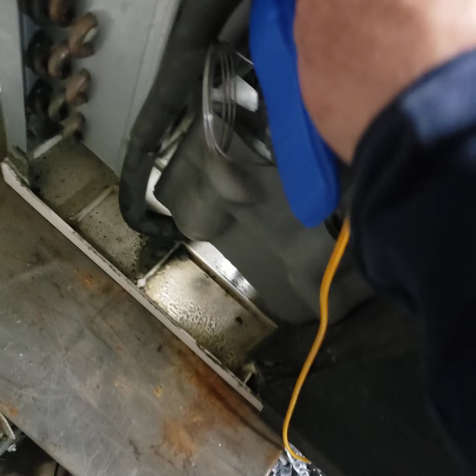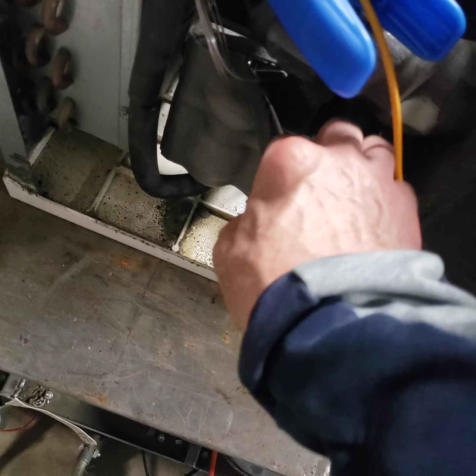It's a little bit tough in here. Okay, so I put it here. You have to always put it at the outlet of the evaporator to check the superheat. Okay, remember, so this is a metering device here. See how it usually freezes. So this is a metering device. The freon comes as 100% solid liquid after it's cooled from the condenser into the metering device, and the metering device will manage.